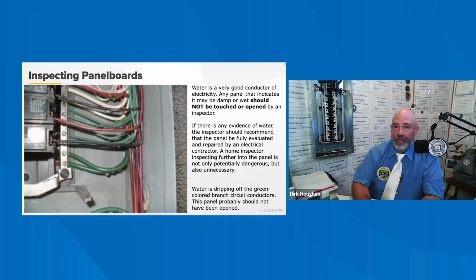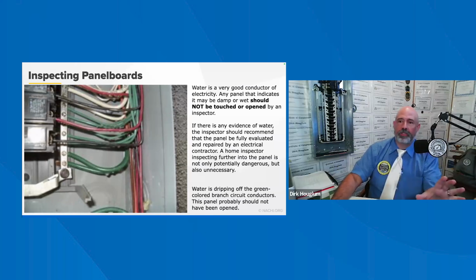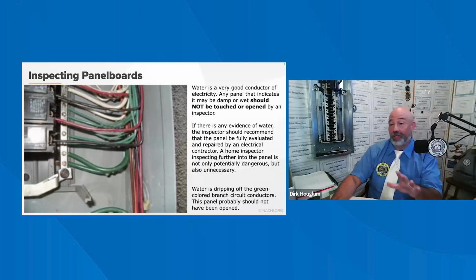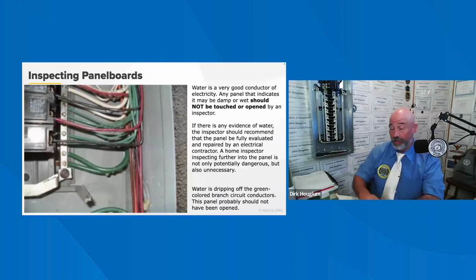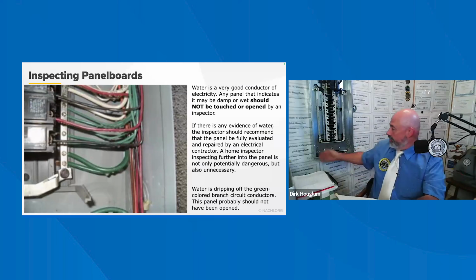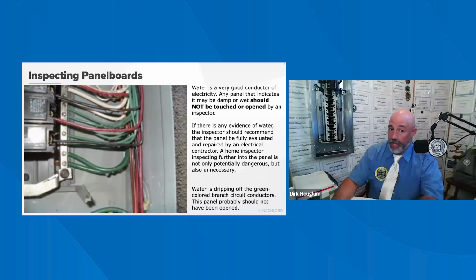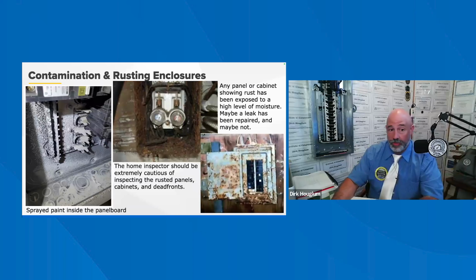Before even thinking about touching, inspecting, or removing a dead front cover, the inspector really should look carefully for the signs of water, moisture, staining, things like that. As we saw with the service entrance, any failures of the mast or cable entry may result in water getting into the panel. You may not know it until you take that water cover or the panel cover off. I've seen it where I took the cover off and there was actually water inside there after the fact. So I just took my pictures and closed it up. I've also seen bees nests and everything else.